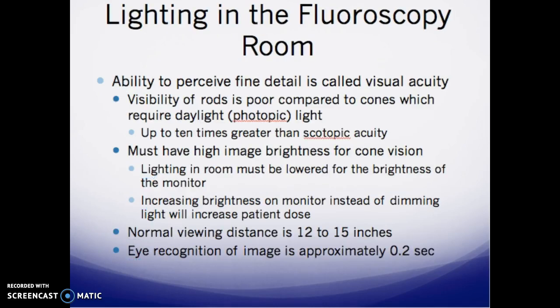Room lighting in the fluoroscopic room affects visual acuity — the ability to perceive fine detail. Rod vision is poor compared to cone vision, which requires photopic (daylight) light and provides up to 10 times greater acuity than scotopic vision. High image brightness is needed for cone vision, so room lighting must be lowered so the monitor brightness is visible. Increasing monitor brightness instead of dimming lights increases patient dose. Normal viewing distance to a monitor is 12 to 15 inches, and eye recognition of an image is approximately 0.2 seconds — fluoro must be on at least that long to assess image brightness.